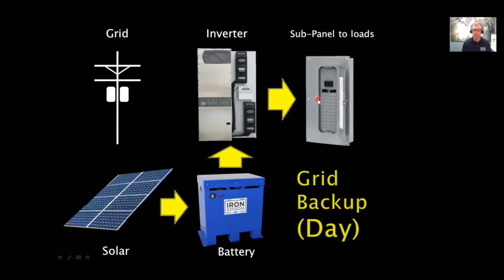So in grid backup, we are self-consuming energy that is produced by the array. And if a cloud comes over during the day and I still need power to supply my loads, that's what the battery is there for. The solar and the battery are wired in parallel, so they're always working together to feed the input of the inverter.